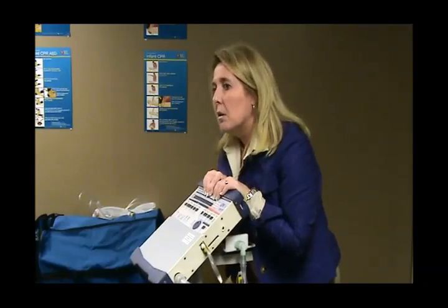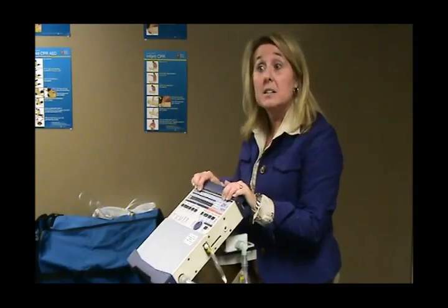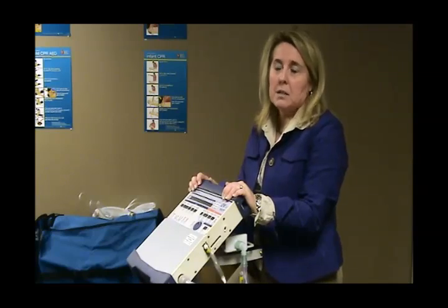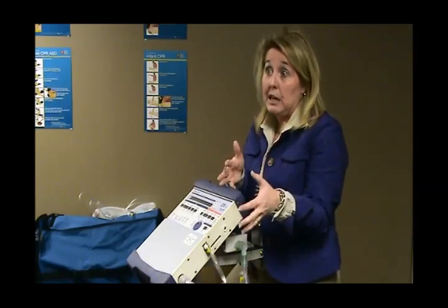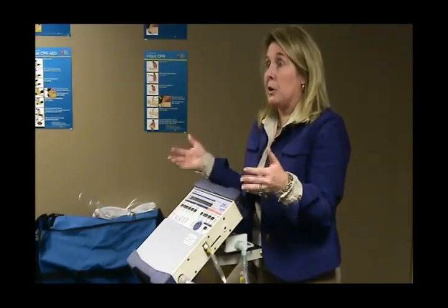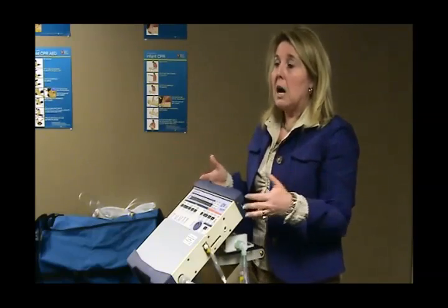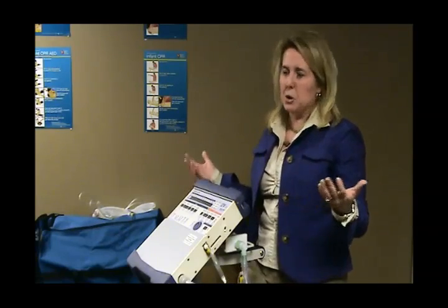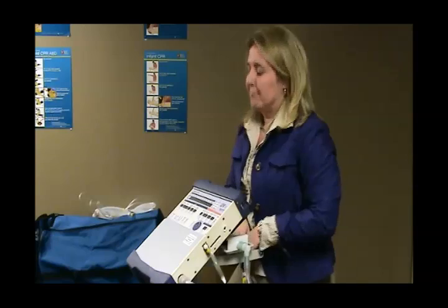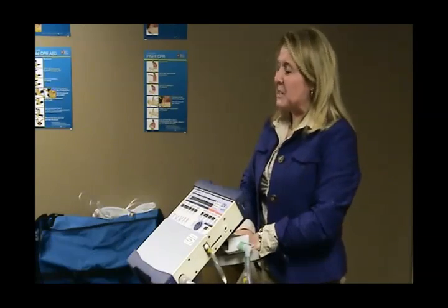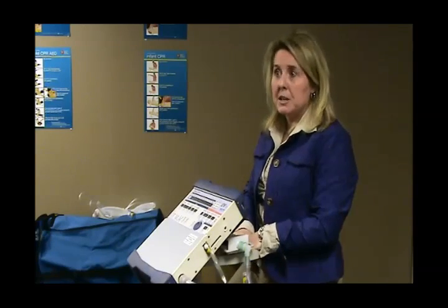What's the PM then? PM stands for preventative maintenance. All medical devices have to have preventative maintenance. Some ventilators it's every year, some ventilators it's every 2 years. We have a new vent out that's every 3 years. So it just depends upon the durability of the vent. They come to the home, take the vent and leave you a different vent. Yep, that's what they do. And it has to go back to the factory usually.